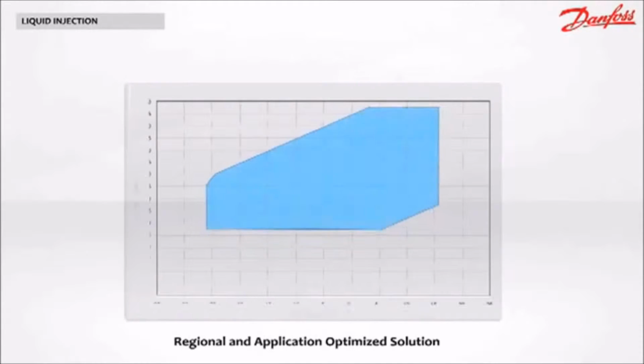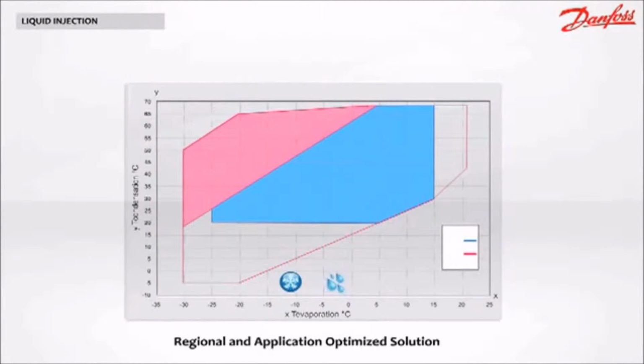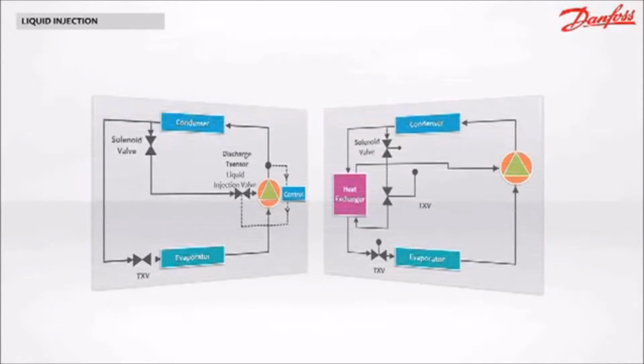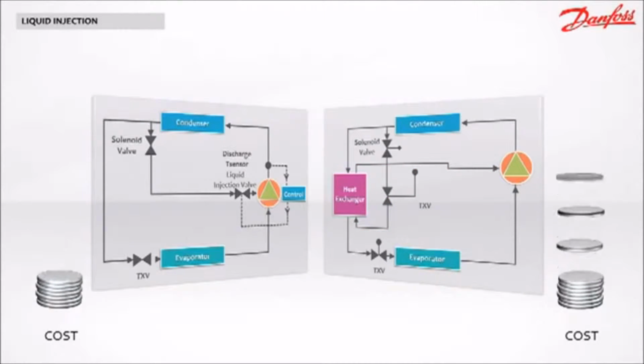The map extension here in red makes it possible for the system to operate under extreme conditions. For instance, a heat pump can produce hot sanitary water above 60 degrees Celsius, even when the outdoor temperature reaches -20 degrees Celsius. If we compare liquid injection with vapor injection, you'll see there is no need for an intermediate heat exchanger, expansion device, and complex piping. With fewer components, you decrease the applied cost of your system.